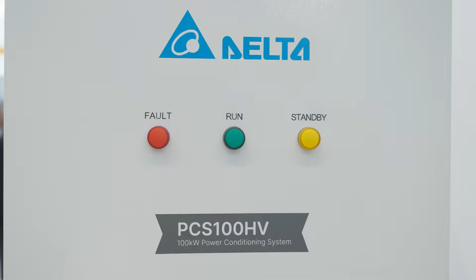Thank you, Hansu, for that overview of PVI products. Continuing with our Smart Energy Solutions theme, I'd like to introduce you to our PCS, power conditioning systems, specifically designed for energy storage systems. The first up is the PCS 100 HV. This particular model is rated at 100 kilowatts at 400 VAC. However, the smart piece is that it's modular and can actually be linked in parallel up to 1 megawatt. It's also able to cope with 3-phase 4-wire installations, meaning it doesn't need a transformer.